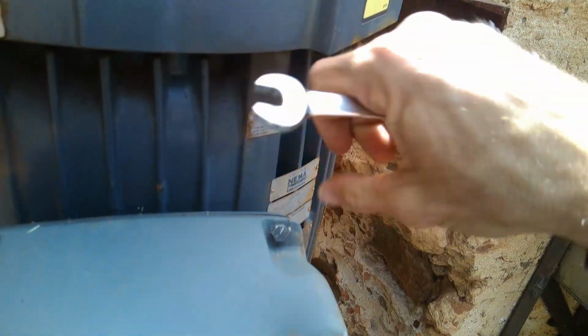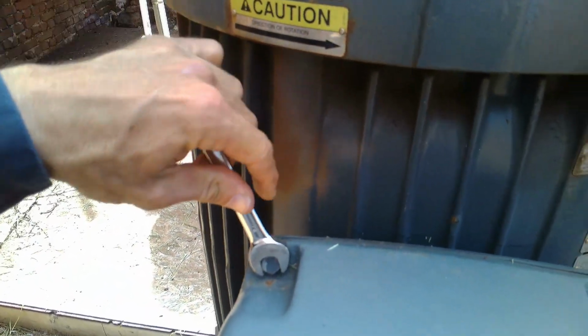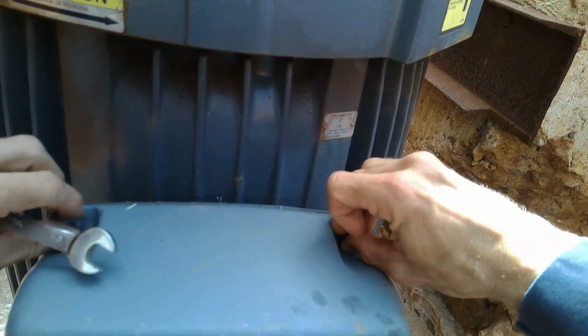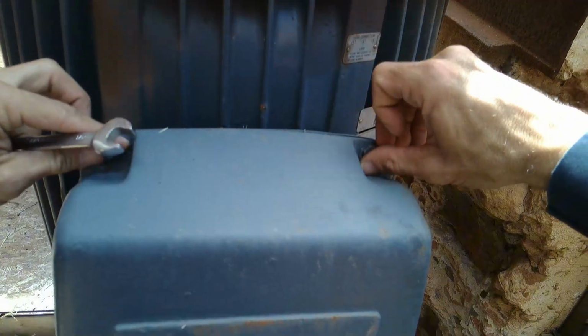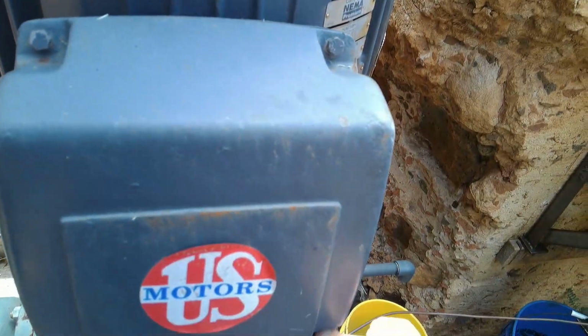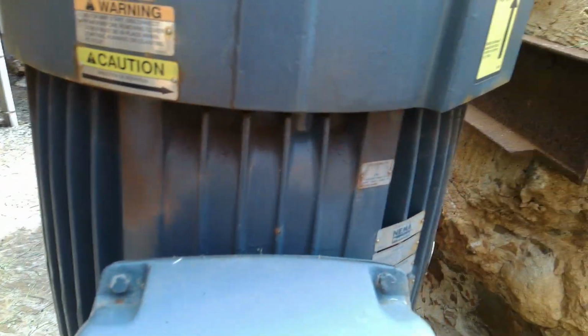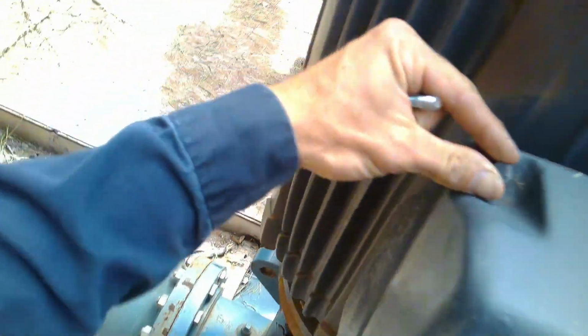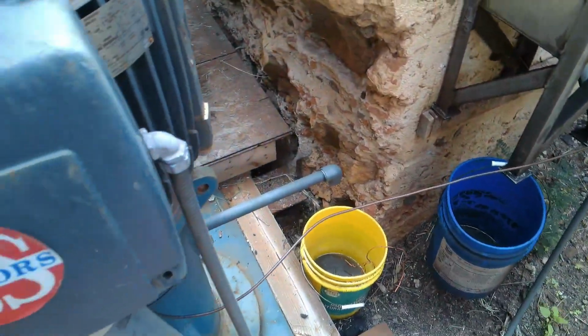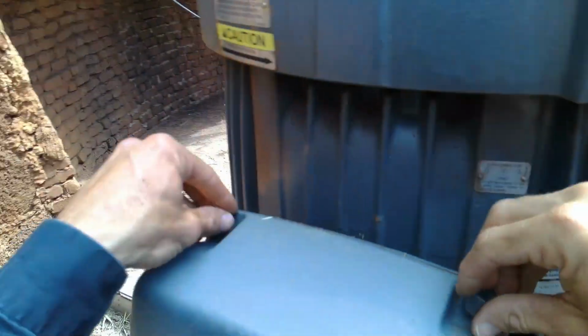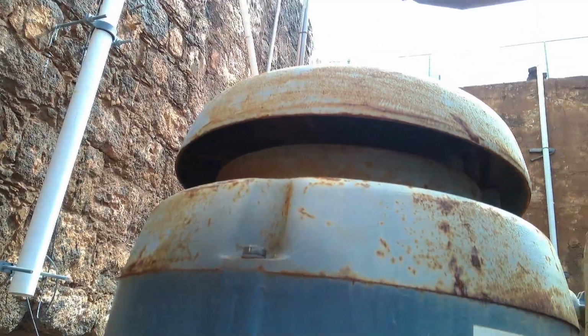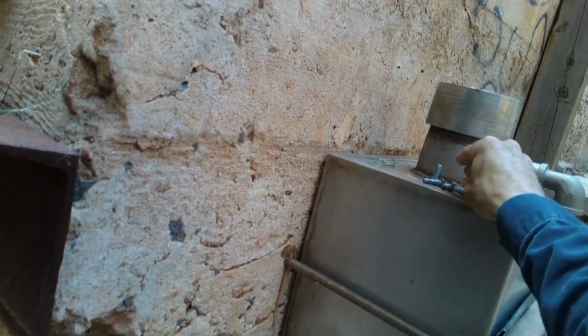Got troubles with the motor, megging it. I think initially I was distracted by the high voltage on the line side of the drive, and I'd never seen that before. And so I thought it was some kind of systemic issue and not an acute issue. And there could be more to this than meets the eye, but at this point, it seems pretty acute. And I can't deny that 2 of my meters saw a dead short inside of this thing. I mean, it's not even like 60,000 ohms or 100,000 ohms. It's just a full-on dead short.